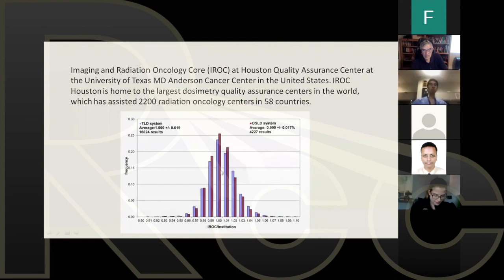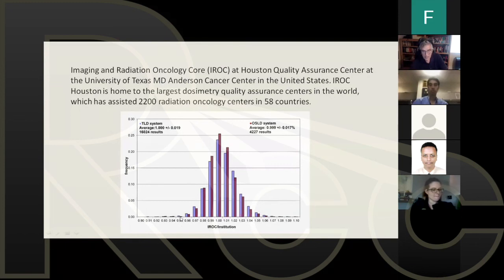Now, the IROC is very good about follow-up. If they find a dosimeter that exceeds 5% here or here, they will give you a telephone call immediately and tell you that your results are off by over 5%. Do you want to check and try again? So they will follow up with a phone call if your results are over 5% off. And if they're consistently over 5% off, let's say you say, no, I'm sure, and you do another batch and it comes out the same way, they will even send a physicist to your center and check the calibration of your machine.